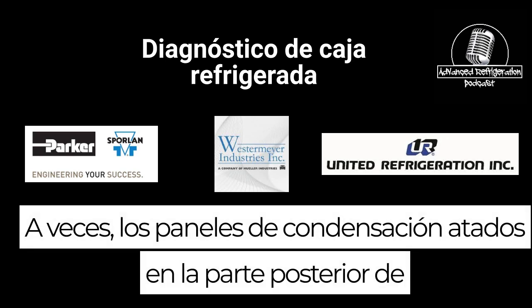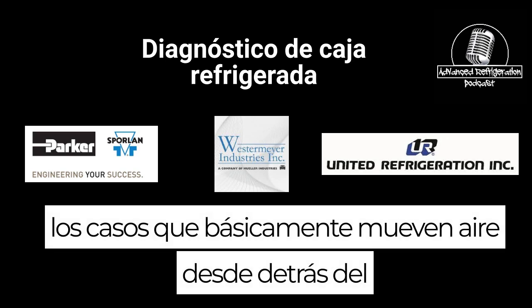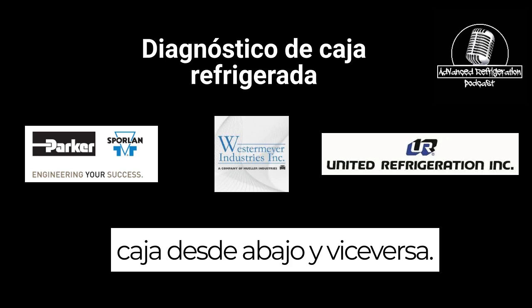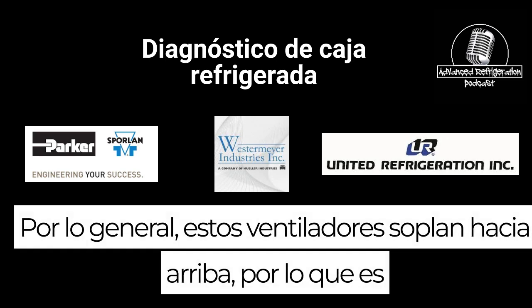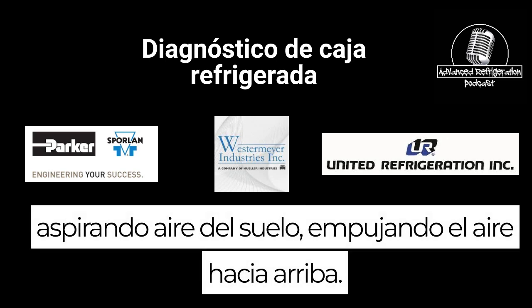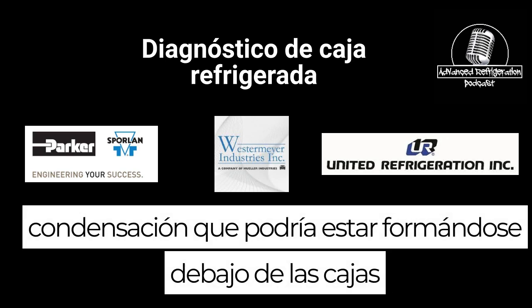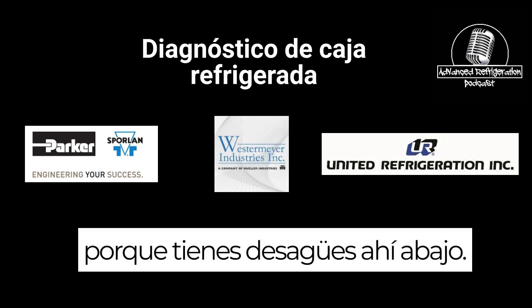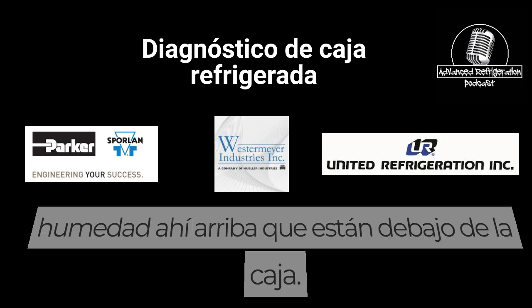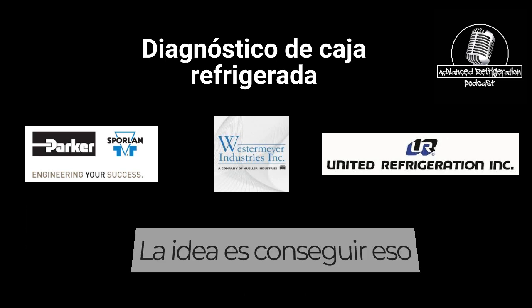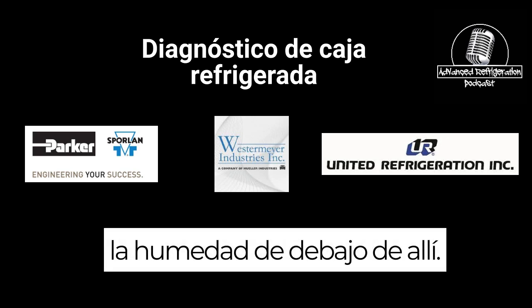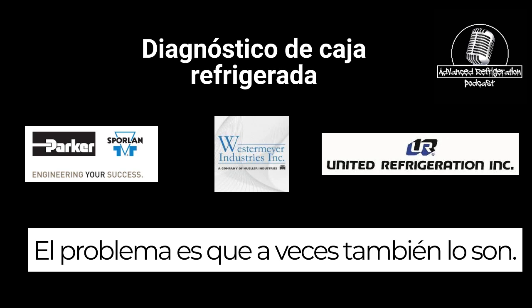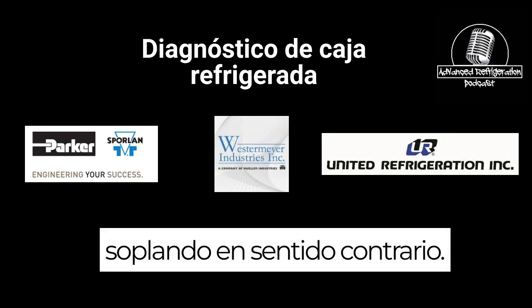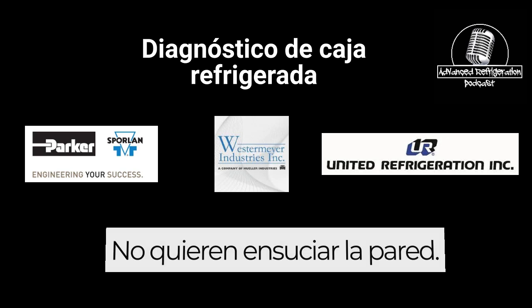Yeah, sometimes you'll also have condensation fans strapped in the back of the cases that basically move air from behind the case out from underneath and vice versa. Usually these fans are blowing upwards, sucking air from the floor and pushing it up to get rid of a little bit of condensation that might be forming underneath the cases because you have drains down there. You have a little bit of humidity underneath the case, so the idea is to get that humidity out from underneath there. The problem is sometimes they are blowing in the opposite direction, especially if the fans are up against the wall. They don't want to dirty up the wall.